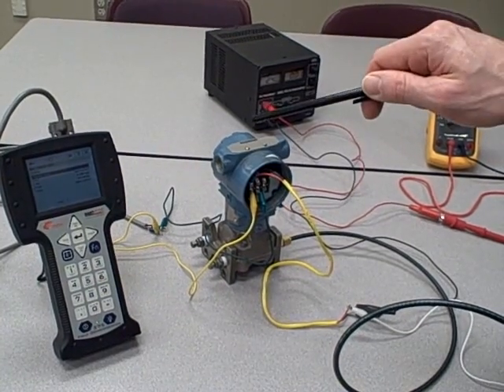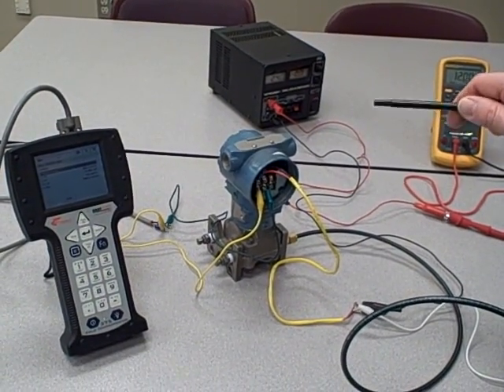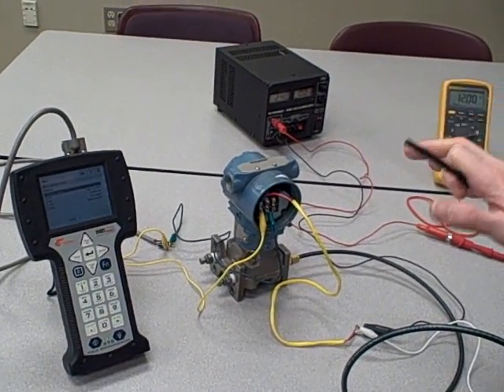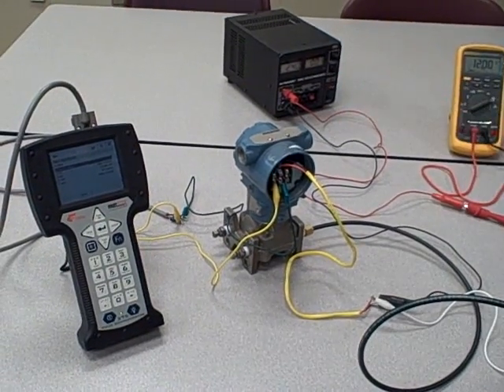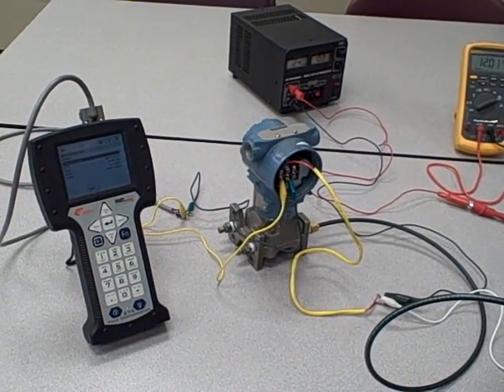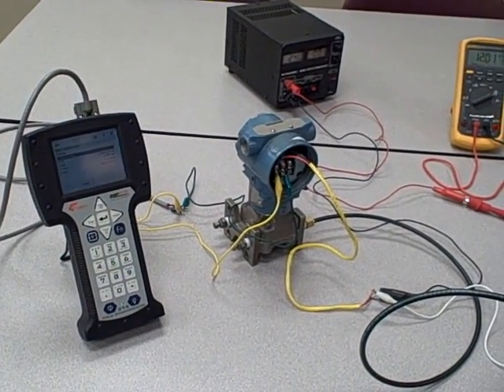We've added to it the capability of superimposing AC voltage and current signals on those same two wires. The transmitter itself is now smart. It has a microprocessor built inside that knows how to interpret and how to send those digital signals.